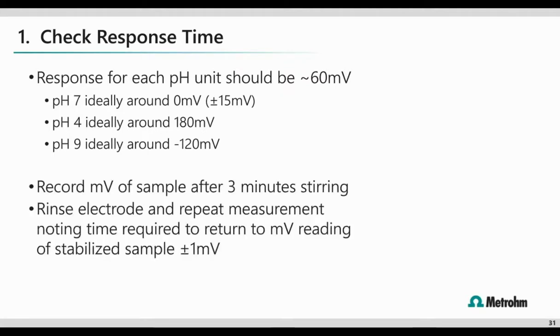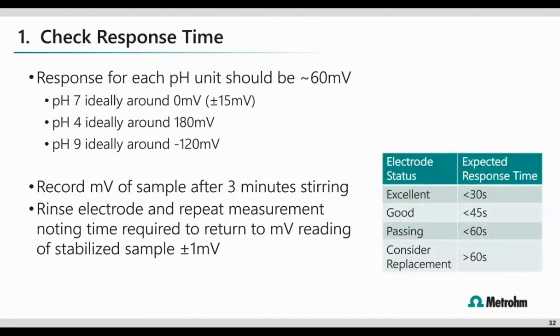The voltage is measured after 3 minutes in a stirred solution and is used as a comparison value for determining the response time. The response time is the time after which the measured voltage has reached this comparison value within plus or minus 1 millivolt. The maximum permitted response time of the pH electrode is about 60 seconds. If the response time exceeds 60 seconds, you may want to consider replacing your electrode.